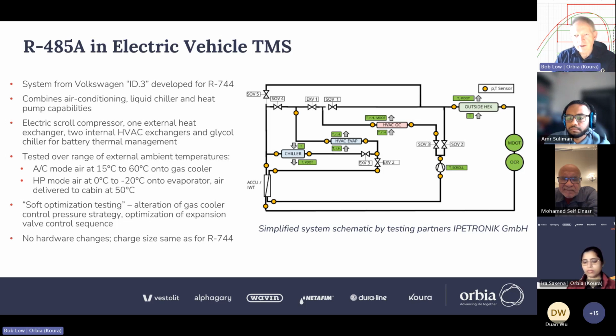So we tested this unit in a German specialist laboratory that works a lot in the automotive systems, called IPETRONIK, and we did air conditioning mode testing, heat pump mode testing, and we did optimization strategy testing. So we didn't change any of the hardware, but we did change the control strategy for the blend, both in aircon mode and in heat pump mode.